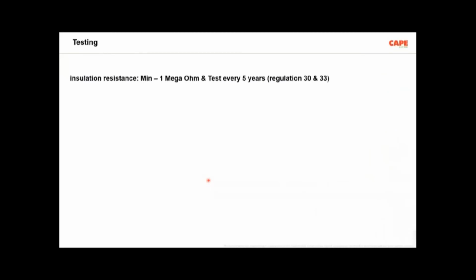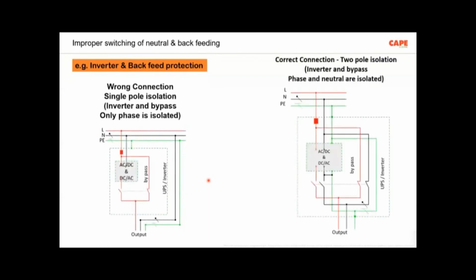With respect to insulation resistance, as I said, regulation number 33 is very clearly mentioned: minimum 1 mega ohm within your electrical installation between current carrying conductors, that means phase and neutral, to earth. Minimum 1 mega ohm. But we always use devices which violate this requirement. One example is the inverter. Most of the inverters which we use in our residences and houses have only single phase changeover. Only the phase is changed over. The neutral is not running through the inverter. The same neutral is circulating everywhere. This can create backfeeding and a shock hazard. A lot of incidents are recorded. Plus, this can also create insulation failures and fire hazards.